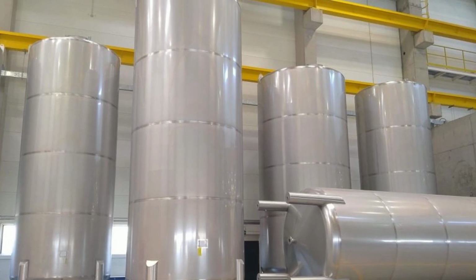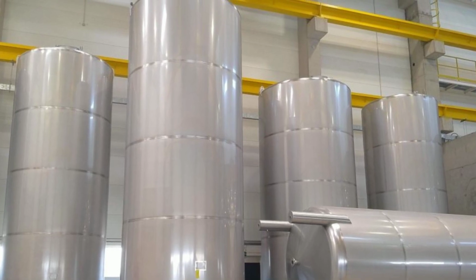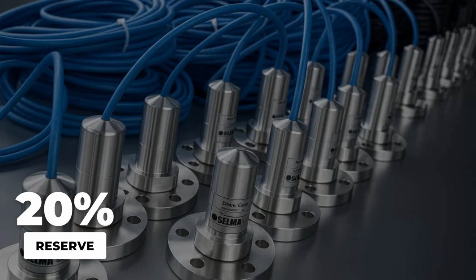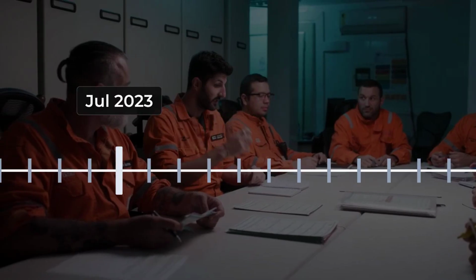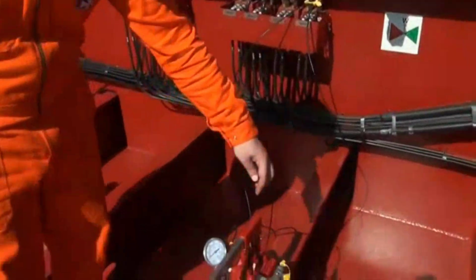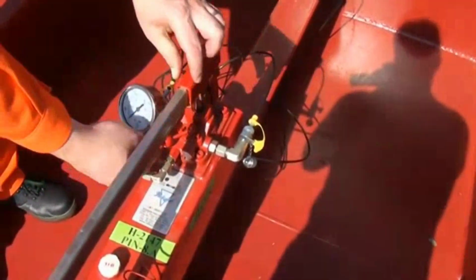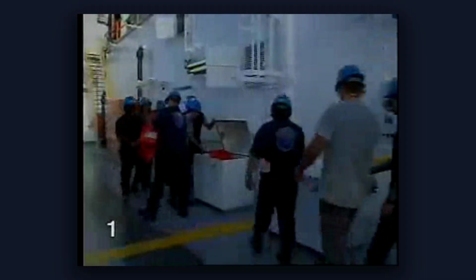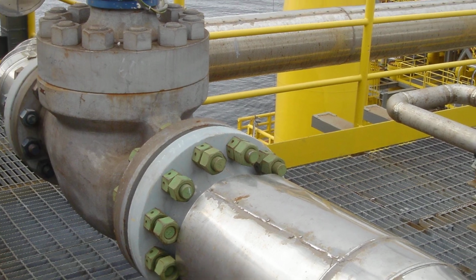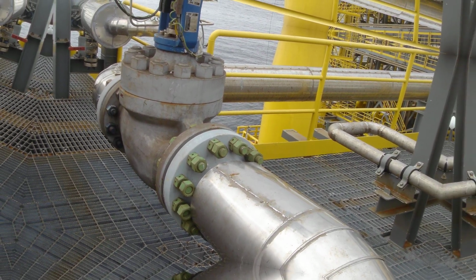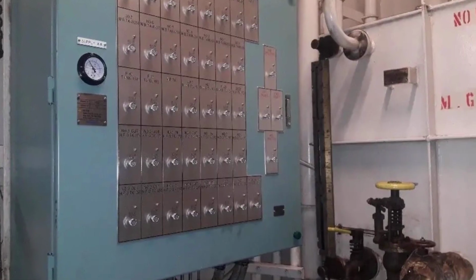Beneath the deck, stainless steel buffer tanks hold a rolling reserve. Level sensors monitor every gallon, and when the buffer drops to 20%, a high-priority alarm sounds in the control room. It is not just a warning, it is a countdown. At that threshold, the platform has hours, not days, before rationing begins. The chief engineer can manually open an isolation valve to bring a secondary tank online, buying time to fix the problem, or if necessary, prepare for evacuation. Every tank is segregated by double-acting valves, preventing cross-contamination if a single tank is compromised.